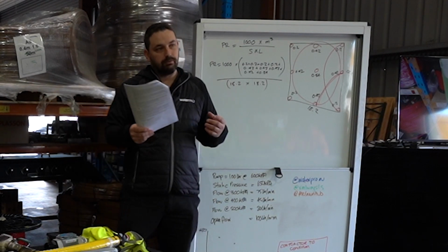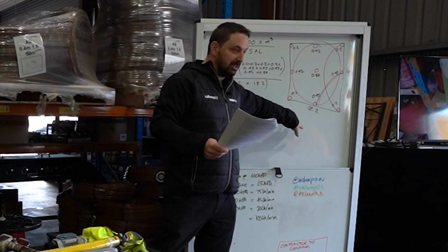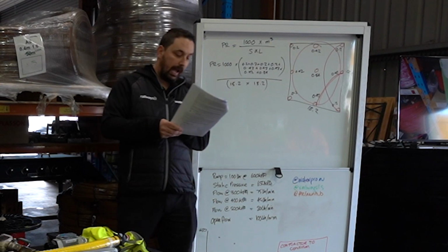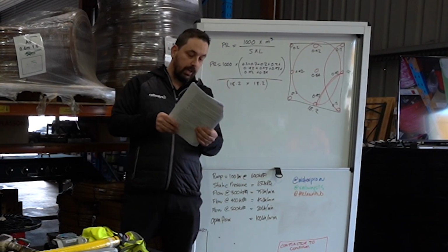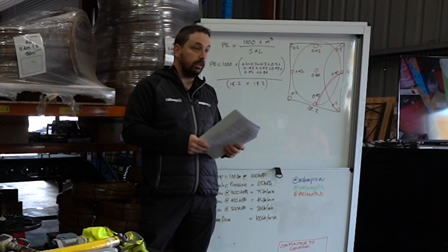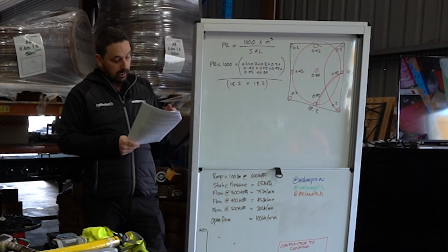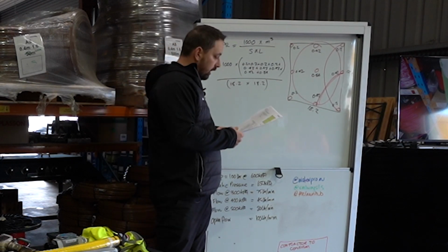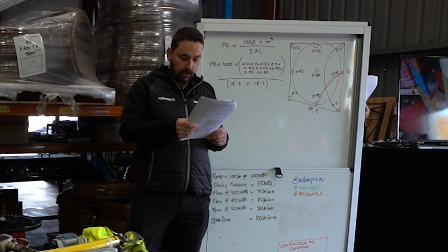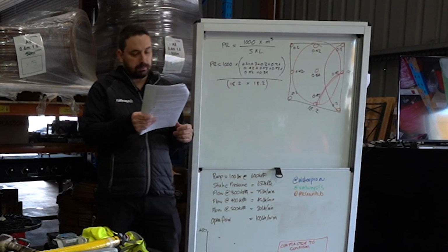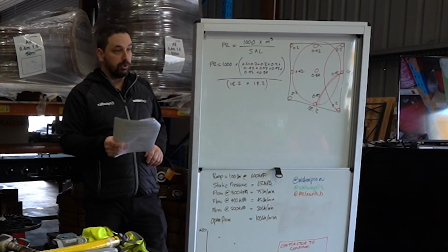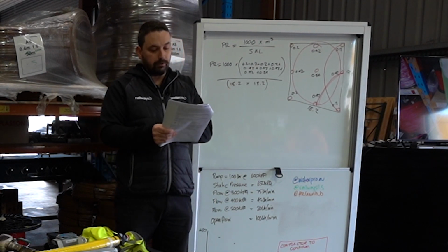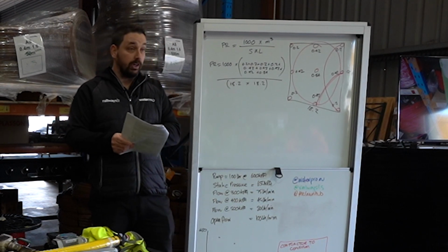So that's why we've done this one at 18.2, just to make it nice and easy for everyone. That sprinkler's at the pressure which, if you go all the way to the other side, you can see is 2.8, which is 280 kPa. That gives us 9.1 metres of throw for a sprinkler. Next to that, you'll see the flow in cubic metres per hour. That's 0.42. Obviously, I'm looking at the 180 degrees, sorry, just to clarify for everyone. If you looked up, you'd have a 0.2 for the 90 degrees.